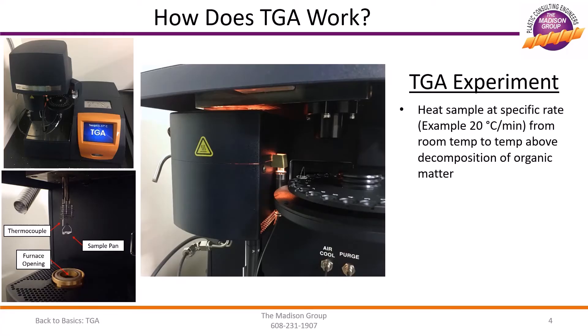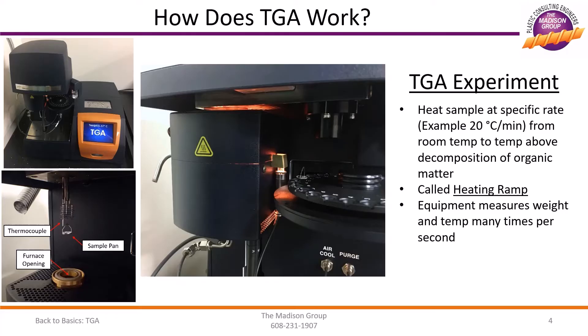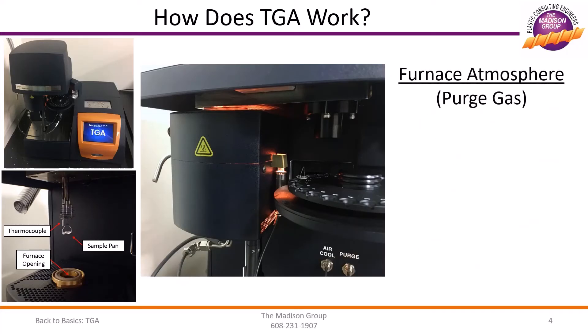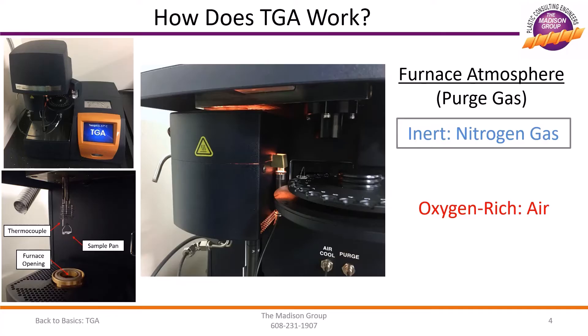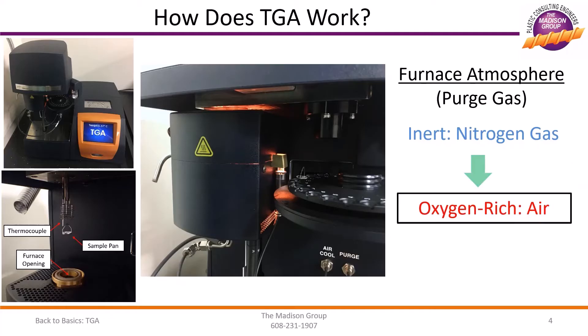A common TGA experiment involves heating the sample at a specific rate, for example 20 degrees C per minute, up to a given temperature. During this experiment, called a heating ramp, the weight of the sample in the pan and the temperature inside the furnace are recorded multiple times per second. This allows the equipment to record both changes in the weight of the sample and the rate of those weight changes as a function of time or temperature. Additionally, the atmosphere inside the furnace is controlled so that it is inert or oxygen-rich. Many TGA experiments involve switching from an inert atmosphere, such as nitrogen gas, to an oxygen-rich atmosphere such as dried compressed air. The reasons for having an inert or oxygen-rich atmosphere will be discussed in the Applications section.